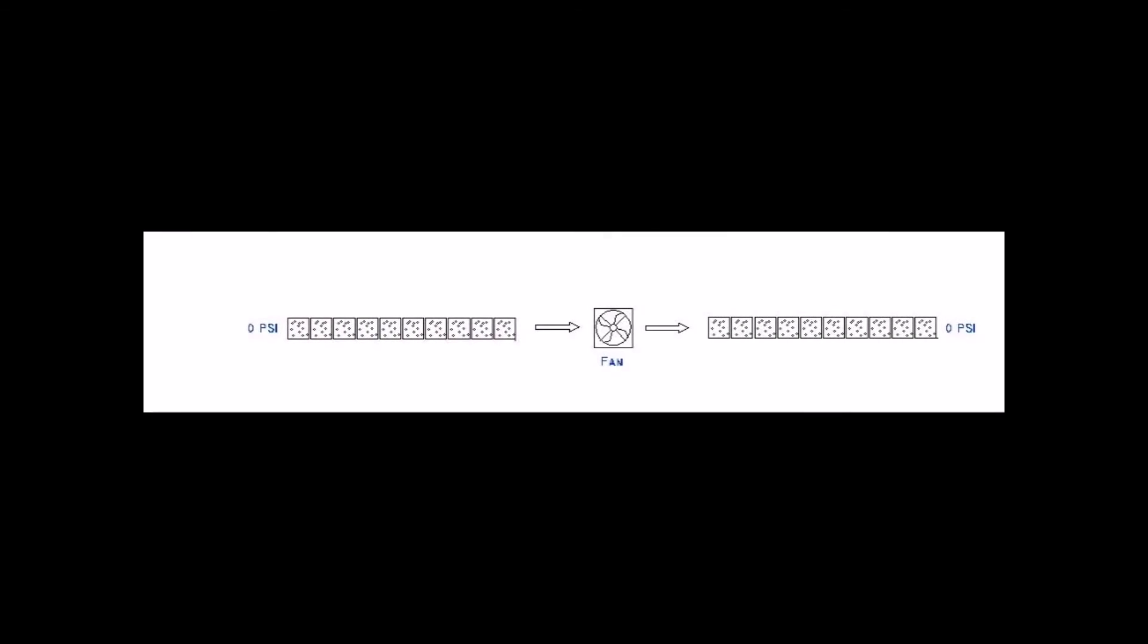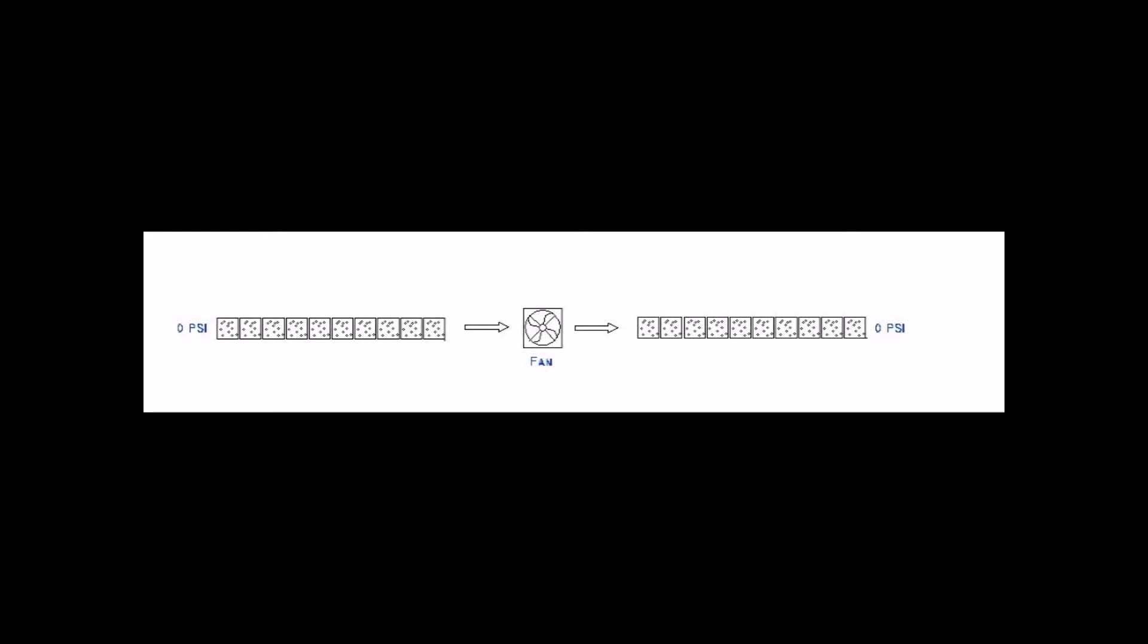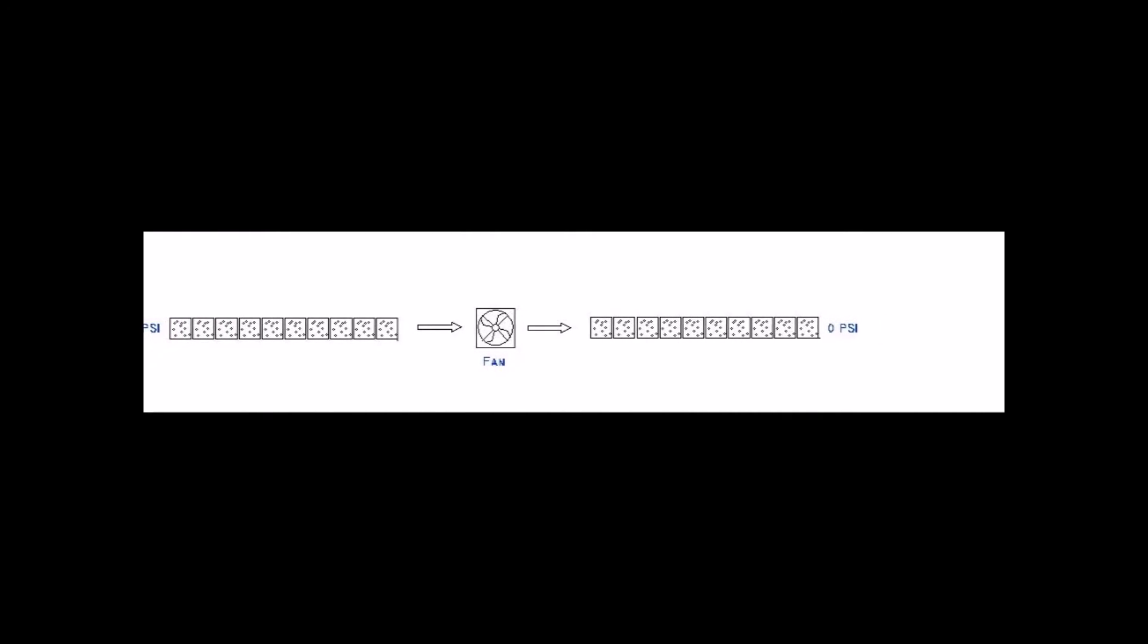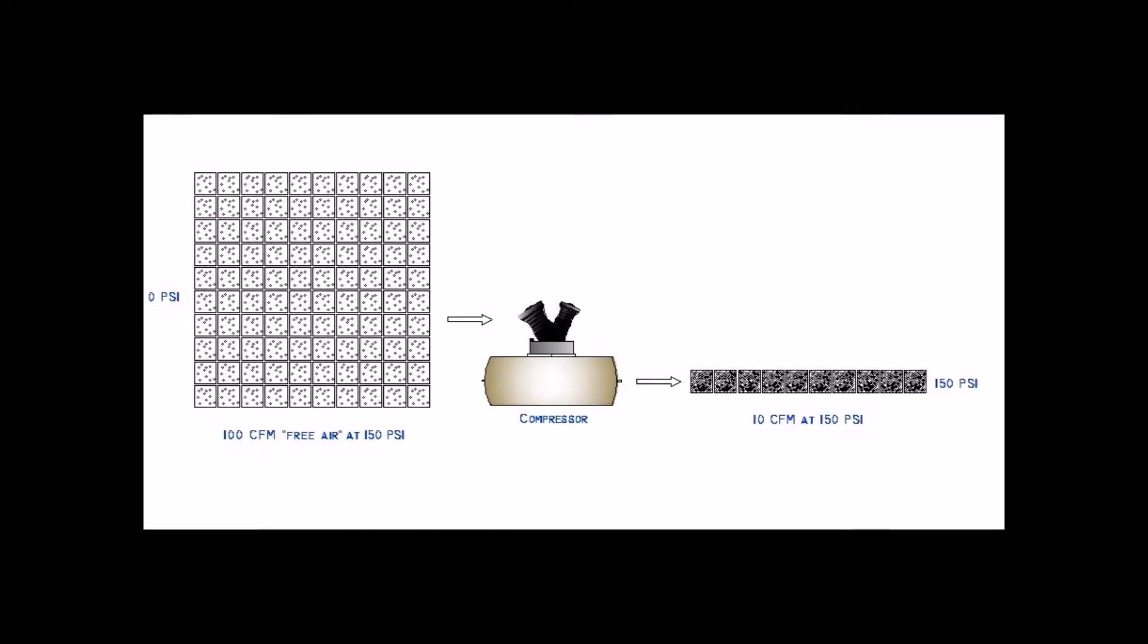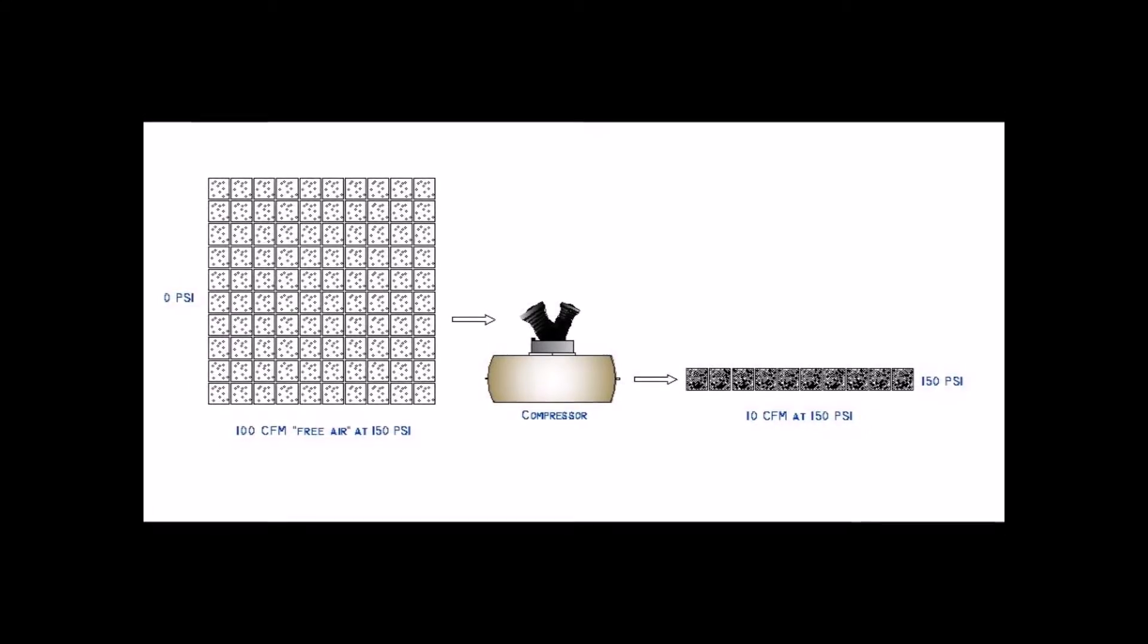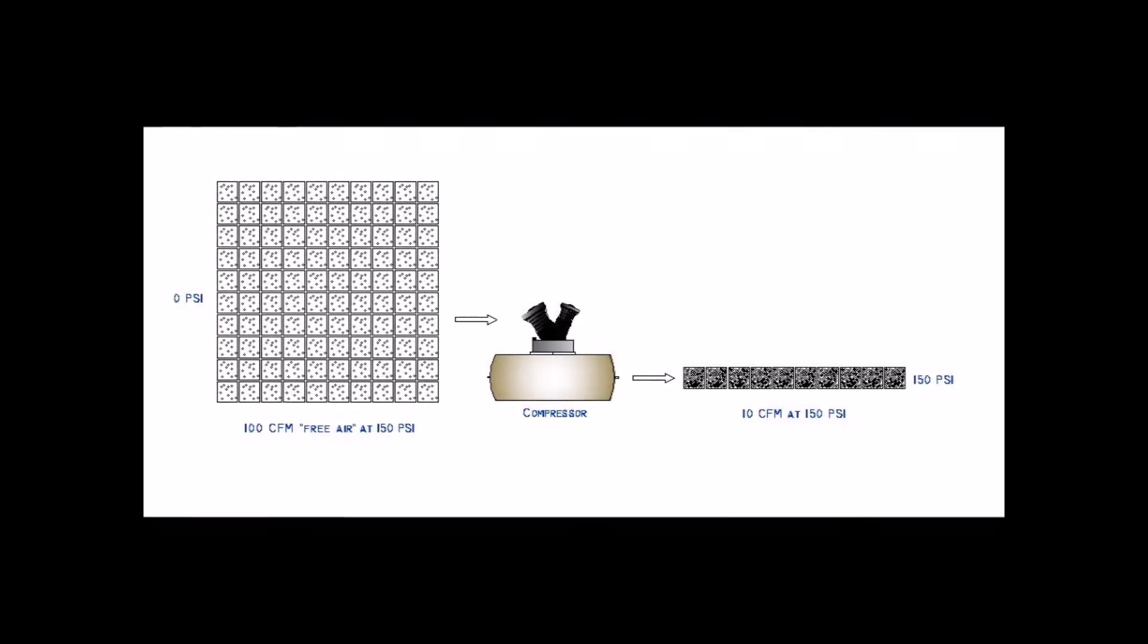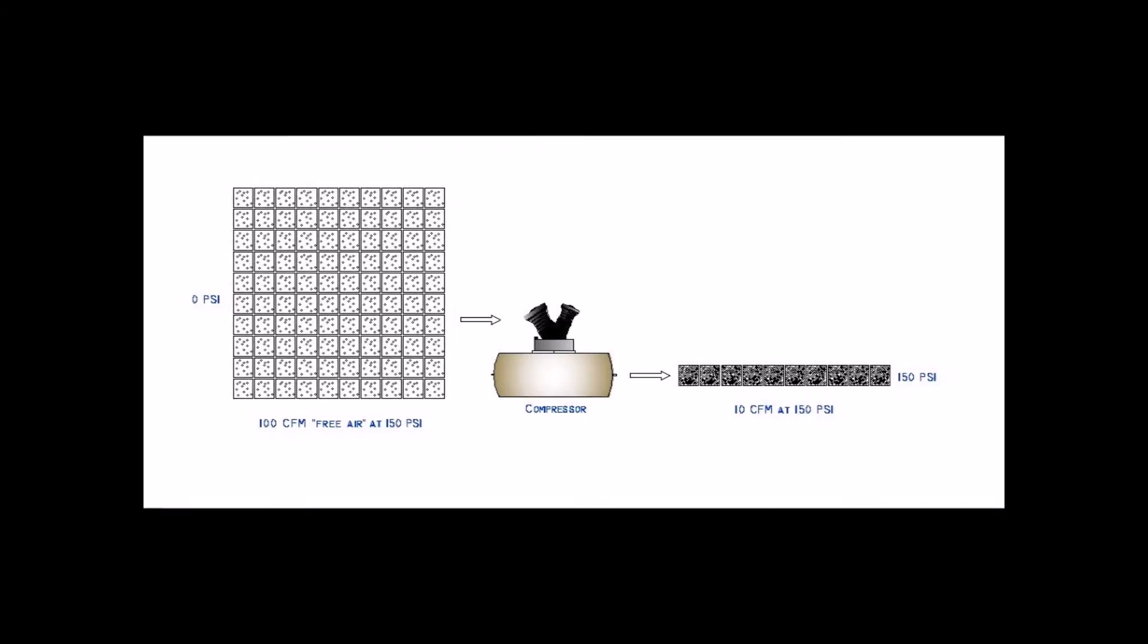CFM should always be followed by the pressure it is at. There is a big difference between a tiny fan that outputs 10 CFM at 0 psi and a big compressor that puts out 10 CFM at 150 psi. The compressor has to take in 100 cubic feet of 0 psi air to make the 10 cubic feet of 150 psi air it puts out.